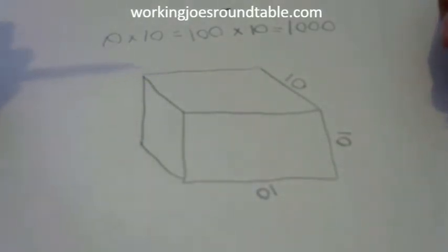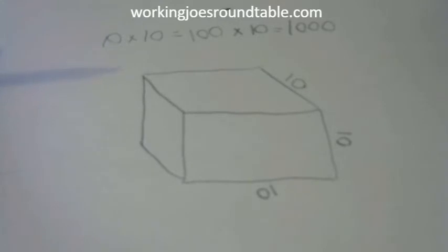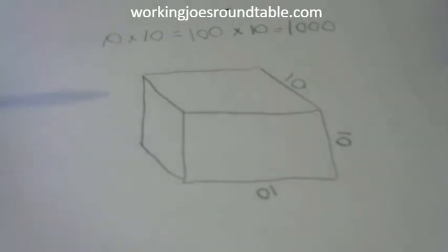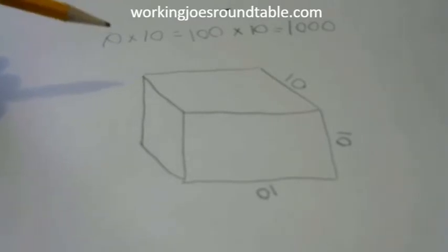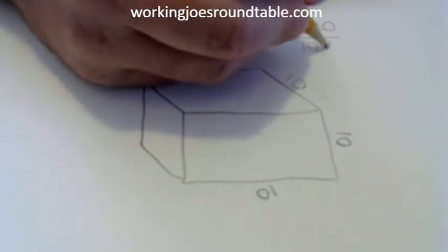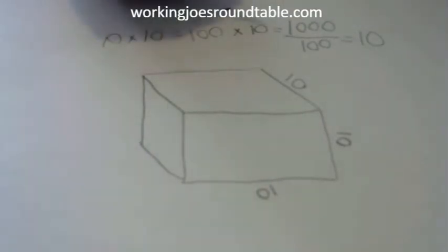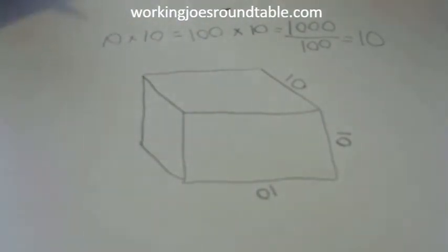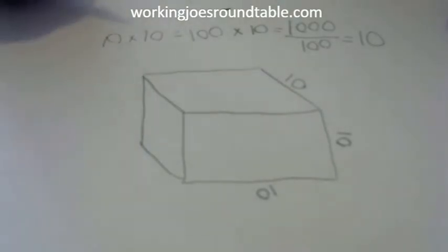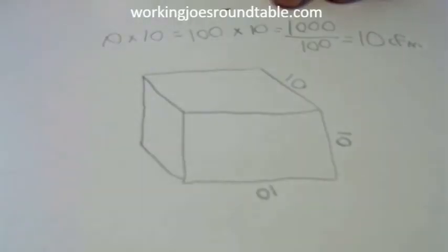So we have a total of 1,000 — that's our volume for this room in cubic feet. Once we have that volume measurement, how we figure out how much outside air this room requires is we divide the volume by 100. So we divide 1,000 by 100 and we get 10. That number is CFM. For a 1,000 cubic foot room, we divide by 100 and we have 10 CFM — that's what we factor in for our load calculation.